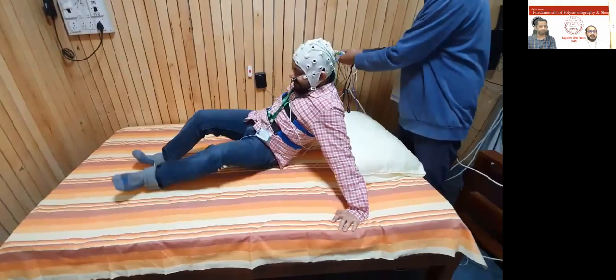There is a question from Mr. Rafiq. Is the pressure transducer cannula not needed, or is only the thermal sensor enough? Yeah, so Dr. Gulshan will be addressing it. The pressure transducer depends on the indication. In case of obstructive sleep apnea, the thermistor is okay. But the pressure transducer is helpful in marking hypopnea. So you can use both the pressure transducer as well as the thermistor, if you want.